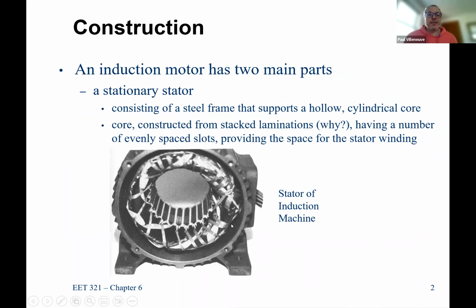So how do you build it? It has a stator and a rotor, just like a synchronous machine. This one is a little more detailed because you can actually see how our rotor circuit is. You can go with a much smaller piece of equipment, whereas a synchronous machine, unless it's your car alternator, tends to be much, much larger. It would be unlikely to see anything less than probably 15 to 25 kW in rating, where again, I could have a 2 horsepower motor, which is only 1.5 kilowatts, so I can get much smaller sizes.